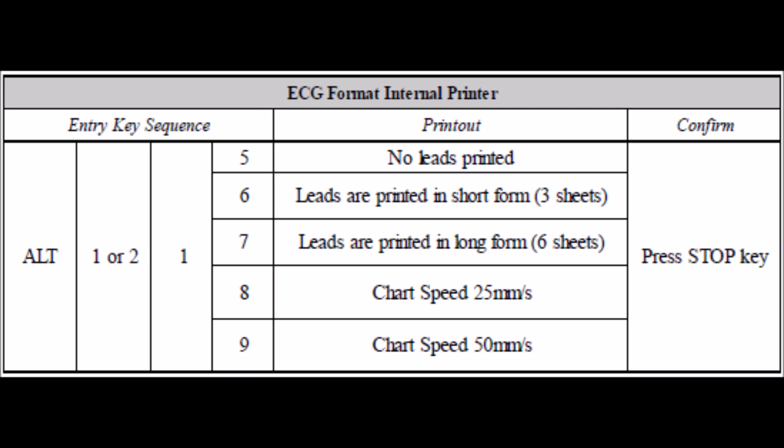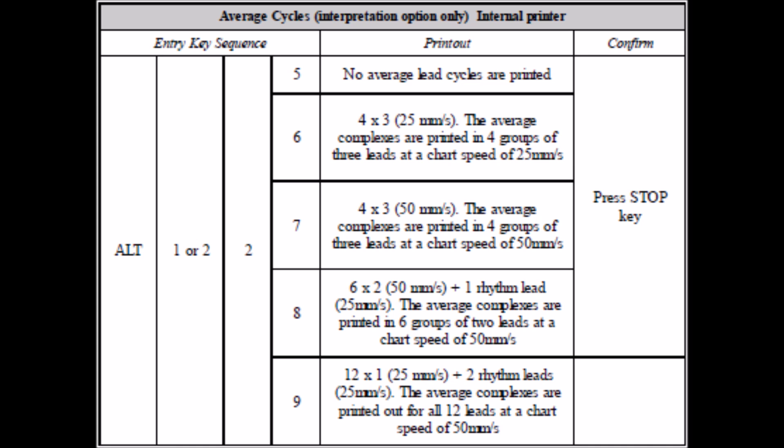To change the settings of format 1 and 2 of the ECG printout, use the following codes. To change the settings of the printout of the average cycles in format 1 and 2, use the following codes.